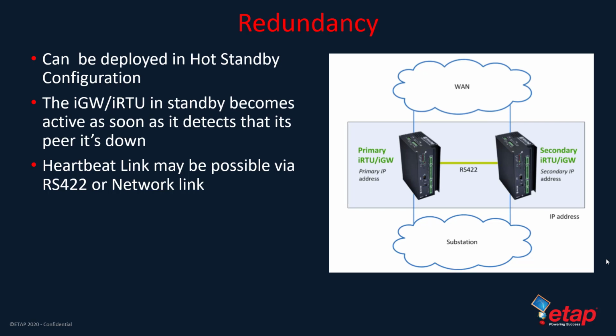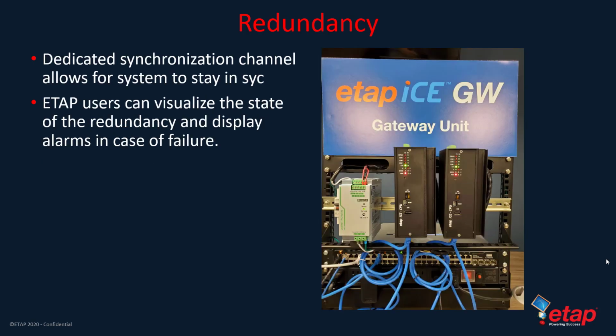This device also offers redundancy. Redundancy works using either a network on your substation, a link on your substation network, or a dedicated synchronization channel. The dedicated synchronization channel allows for the two devices to be always in sync and also understand the state of each other.